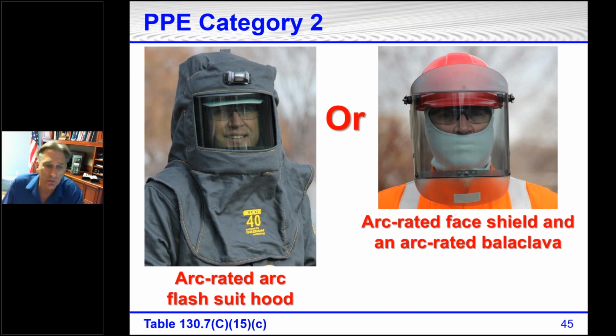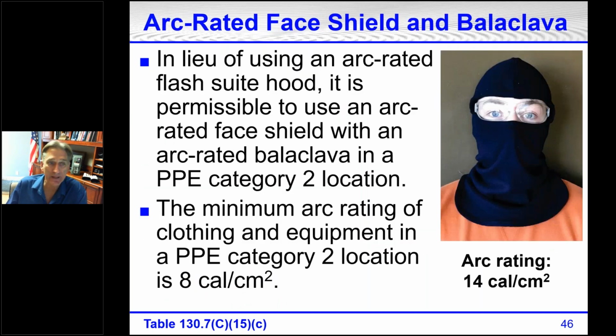With category 2, you can either wear an arc-rated flash suit hood, or an arc-rated face shield and arc-rated balaclava. Instead of using an arc-rated flash suit hood, it is permissible to use an arc-rated face shield with an arc-rated balaclava in a category 2 location. Minimum arc rating for clothing in category 2, as we looked at a while ago, was 8 calories per square centimeter.